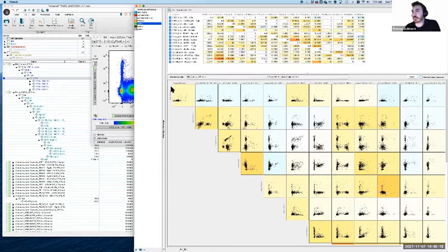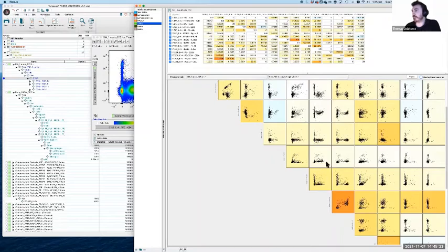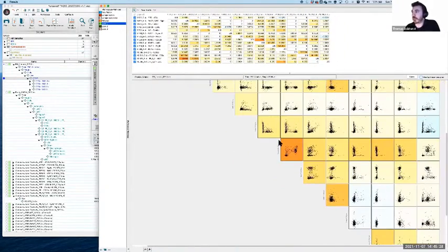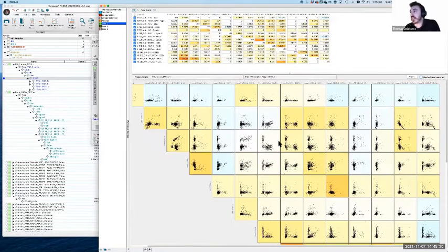So this is basically a matrix of every fluorophore and detector pair. We can explore each of these combinations and go hunting for where there might be problems. The problems are that leaning we were talking about before, that classic curve. There are going to be some problems here, because I know there are, because I made problems. There will be some areas we might flag early on, and then discover that's totally fine, or it's spreading error we can't do anything about. So we'll go hunting and see what we come across.